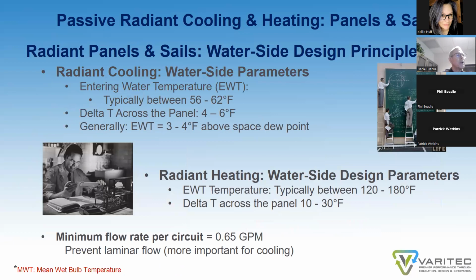So, looking at radiant cooling from a water standpoint, entering water is typically between 56 and 62 degrees. You don't want 44-degree chill water in a space, because that is far below space dew point of 55 if the room is conditioned to 75 degrees, 50% RH. So you want warmer chill water, 56 to 62 degrees.